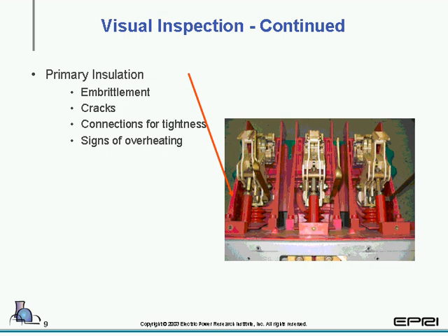The next one we're going to take a look at is the primary insulation, and you should be looking at that currently on your screen. Now, this particular one is red, but for other manufacturers it may be black or a different color. You may need a flashlight to see if there's some sort of problem or cracking. Sometimes you visually can't see them with the naked eye. And many times you will see cracks where there's an insert and where the bolts will go through and are tightened down into the insulation.